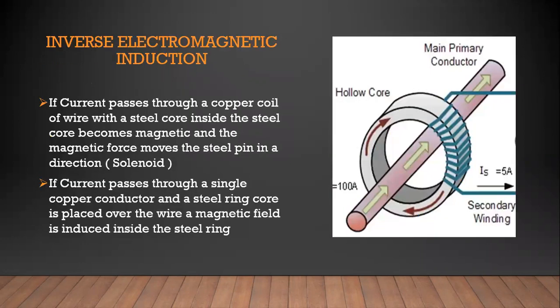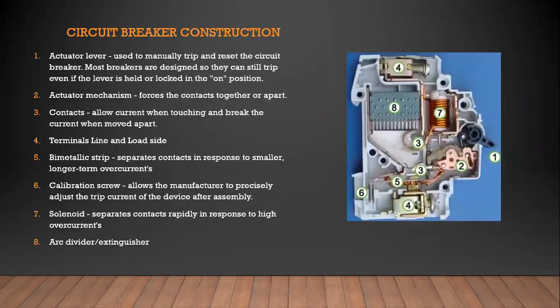I've got the electromagnetic induction. If a current passes through a copper coil or wire, the steel core inside becomes magnetic. And this principle is very important for you to understand the basic operation of an earth leakage device, because there are few people that actually understand how earth leakage works. And once you understand the electromagnetic principles, it will make your life much easier in a maintenance or a repair situation. I've got circuit breaker construction in there.